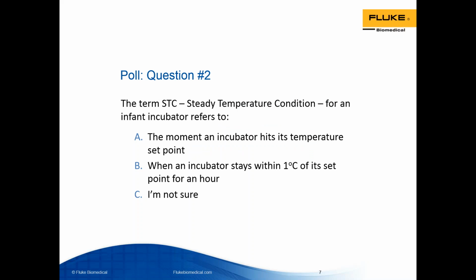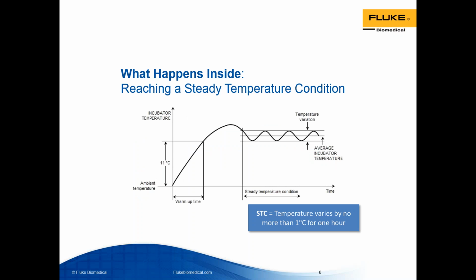Great, thanks, Jamie. So good job to the 81%, because STC, the steady temperature condition, is the condition that's achieved after the incubator does remain within 1 degree Celsius of the set point for an hour. So here's a visual of what's going on. When an incubator is first turned on and a temperature is set, say, at 36 degrees Celsius, temperature mapped over time looks like this, with temperature on the y-axis and time continuing on the x-axis.